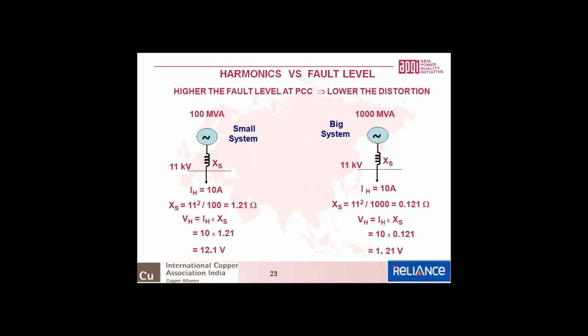Another important aspect is the effect of harmonics. Let's say a harmonic current of some amps flows; how does it affect a small system and a big system? By a small system we mean one in which the fault levels are very low, whereas a big system is one where the fault levels are extremely high. Now, I have given you two examples.